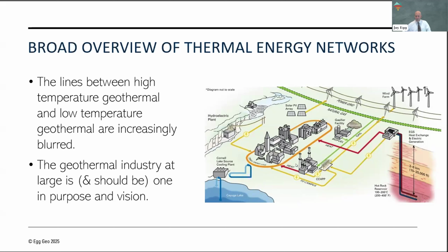Well, they've started changing that. One of the first things they did, part of an energy network, is geothermal. They found that the local surface body, Lake Cayuga, had a 40 degree temperature year-round at the bottom of the lake. So they put in what they called the Cornell Lake Source Cooling Plant, which simply by running pumps and circulating water creates almost all the cooling they need for the campus without even running chillers. That's surface water geothermal exchange at its finest, especially for cooling.